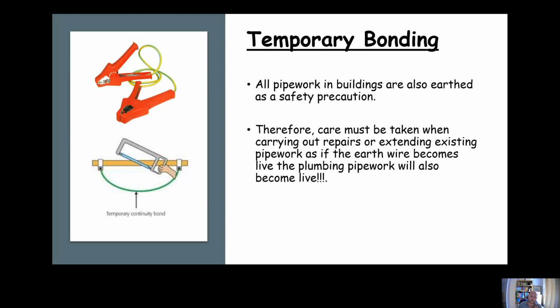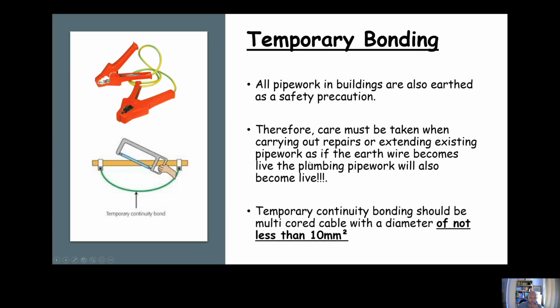So what we should always do whenever we cut into a piece of pipework on an existing property is put a temporary continuity bond on each side before we cut. Worth noting, a temporary continuity bond is made up of multi-core cable, lots of thin strands inside, and it should be at least 10 millimeters in diameter.